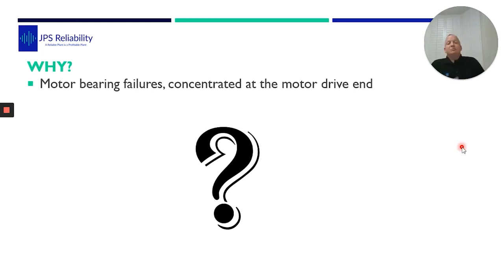So we sat down, we showed them all the data, and said, right, well, why is this failing? Why has it not failed before? There are so many different stories about things setting on fire, and he did this, she did that. But basically, a long time ago, they used to run the motors at full speed. They used to just step them up to max speed and let it run. Then the energy efficiency team did some tests, and they worked out it's more energy efficient to run it slower.